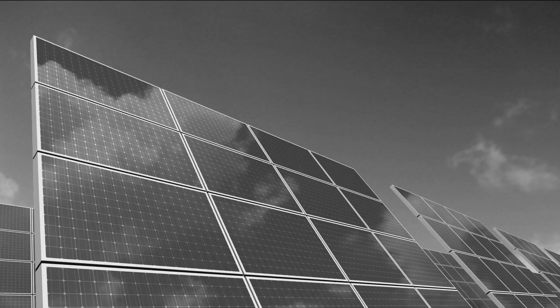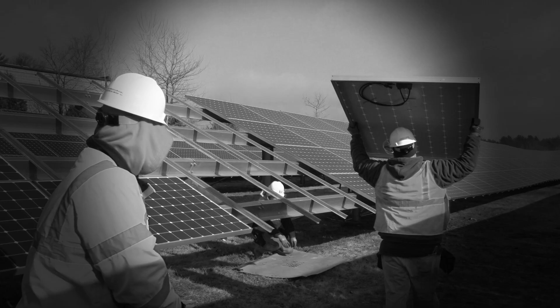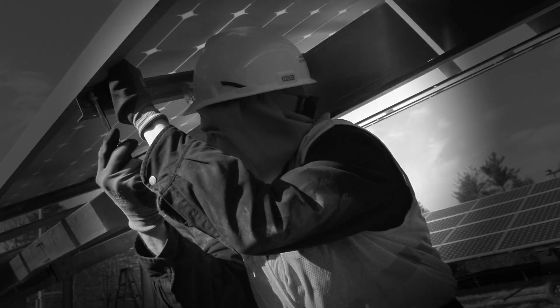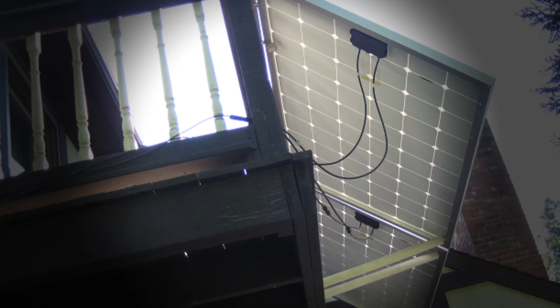All parts of a solar system, whether it's on your roof, in a parking lot, or in a field, per the State of Massachusetts Division of Licensure, Electrical Division, have to be installed by licensed electricians. It's the safest way, it's the best way, and it's the right way. More and more the racking systems are becoming an integral part of the grounding, so the racking has to be laid down by electricians. It's a piece of the bonding and grounding of the system. But all in all, like any other electrical system we install, a piece of switch gear, anything, there's an inherent danger in it being hooked up improperly.